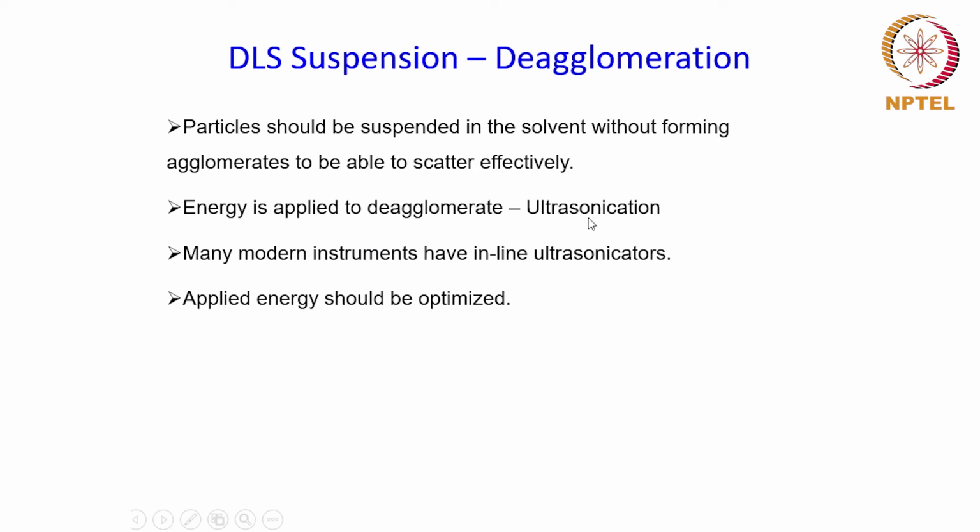For example, the suspension can be subjected to ultrasonication for a particular period of time with a certain amount of energy, which will ensure that the agglomerates, if there are any, will break and the particles will be suspended in the liquid individually. And many modern instruments, in fact, are equipped with inline ultrasonicators to do the job. And when you do this ultrasonication, the applied energy has to be optimized. And these kind of instruments can even do that as well.